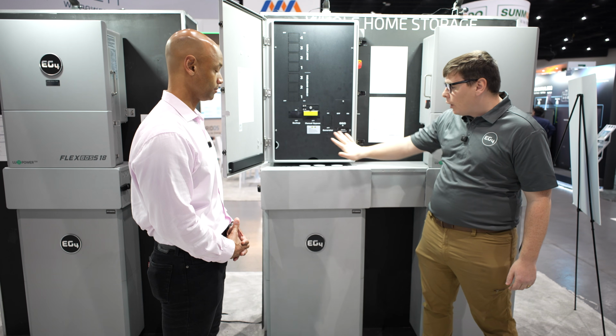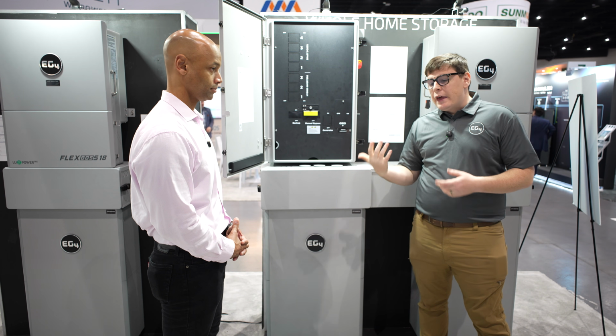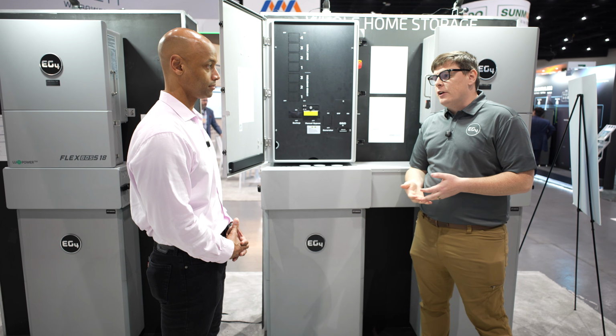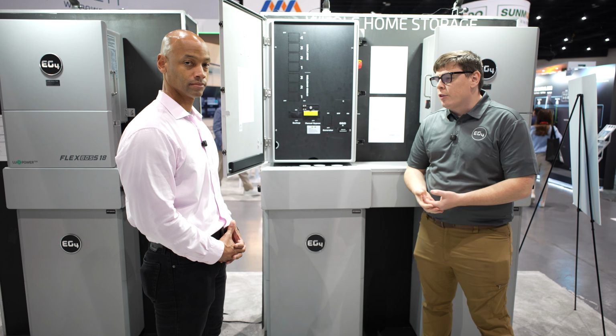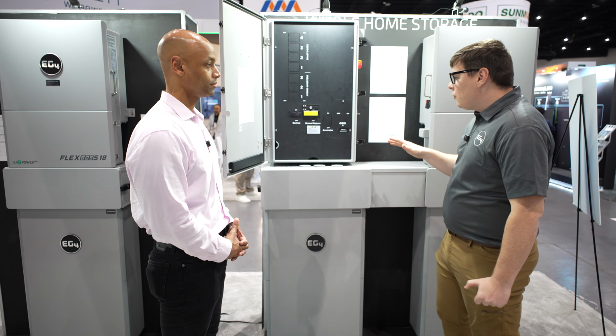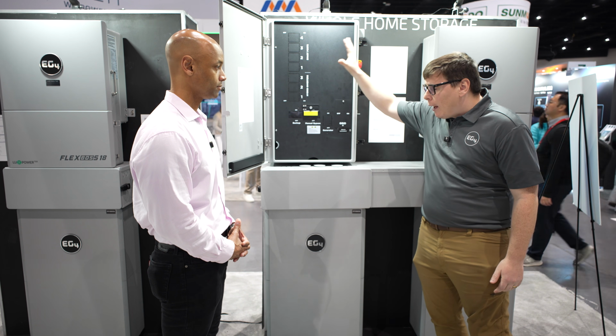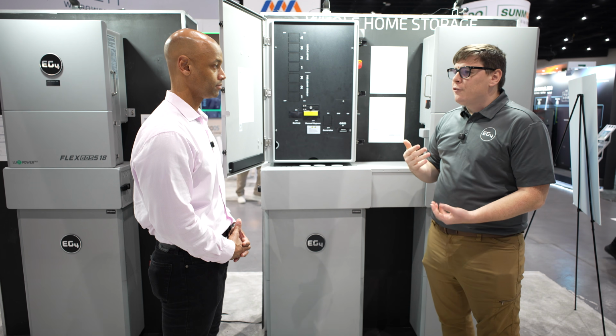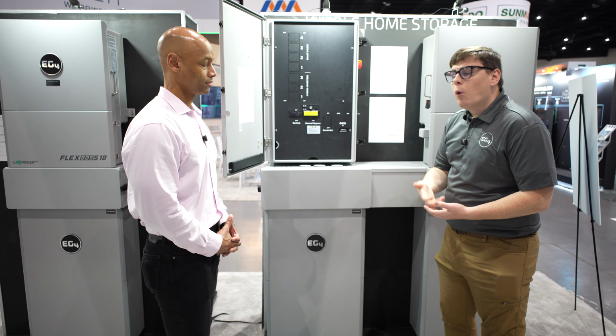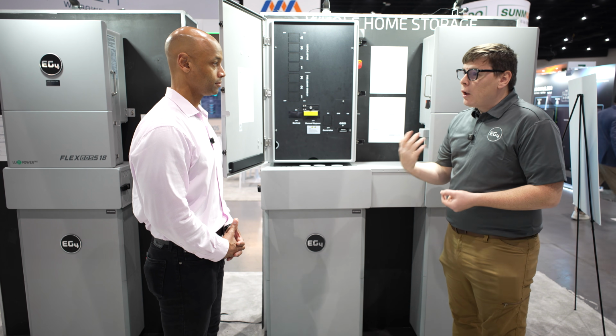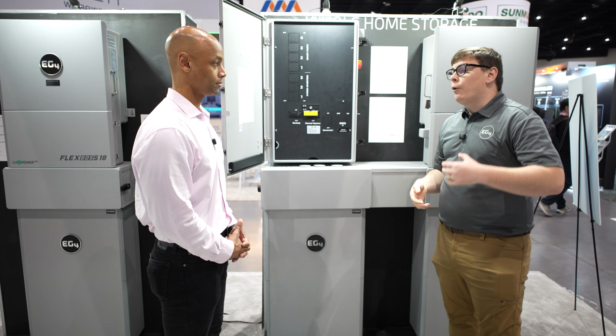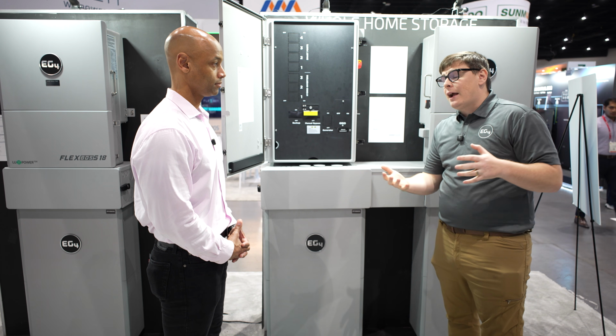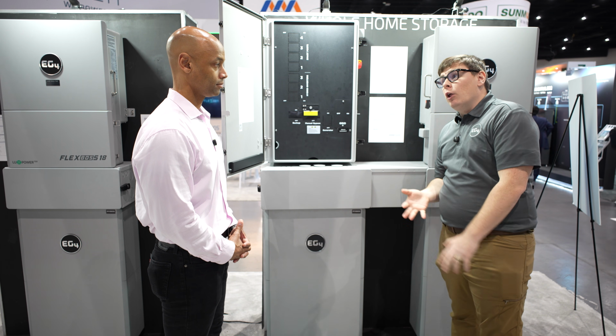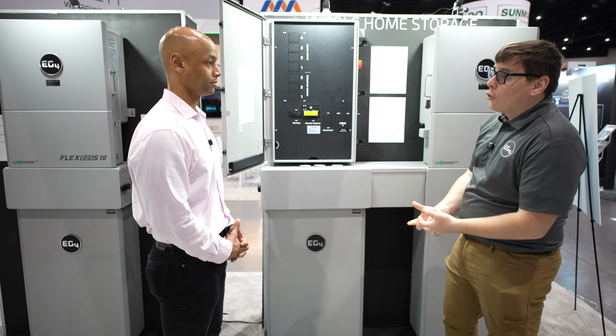It also allowed us to get a fully automatic dark start feature, which we're going to do all the training for this coming month. And that is, you put the whole house management here. But if you have just a 100% AC coupled customer who already has a solar system, they run into a dark start problem where whenever they're in backup mode, they could run their batteries so low that the backup inverter has to turn off.